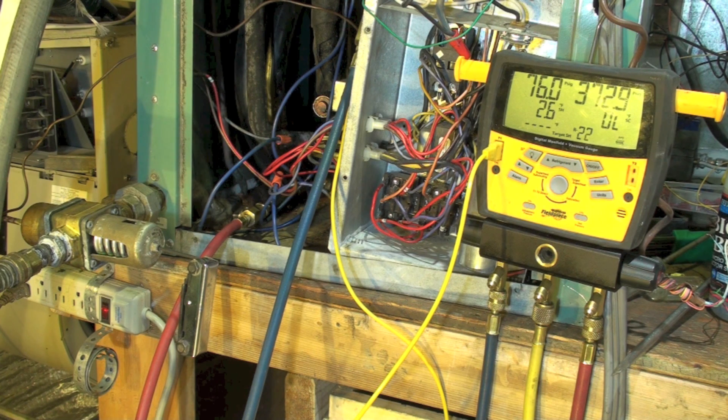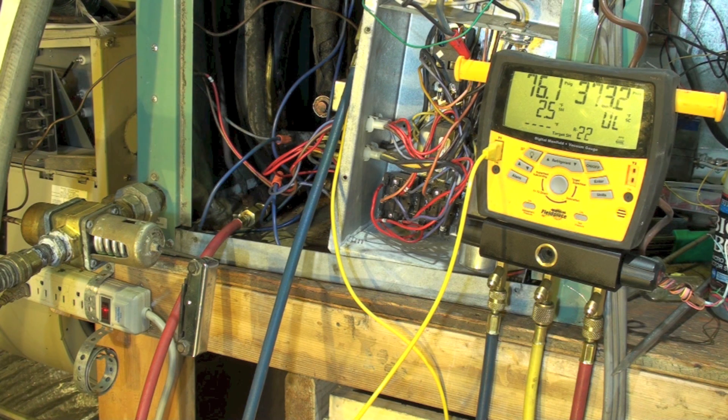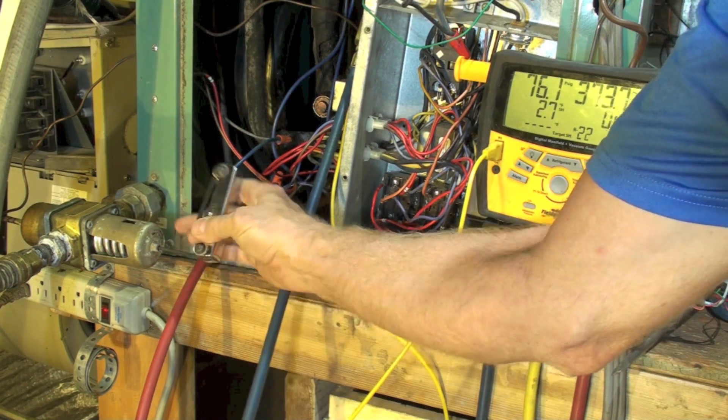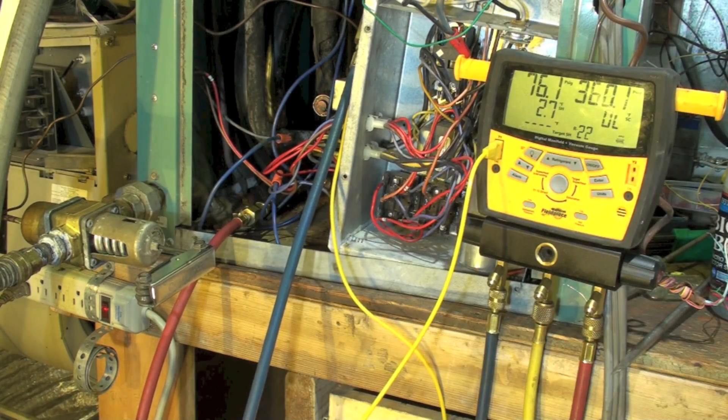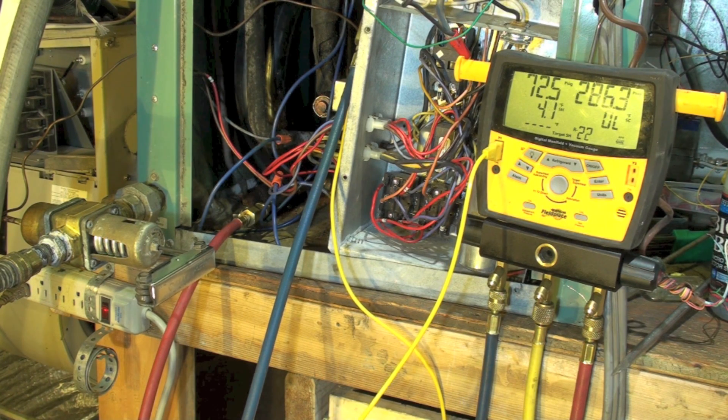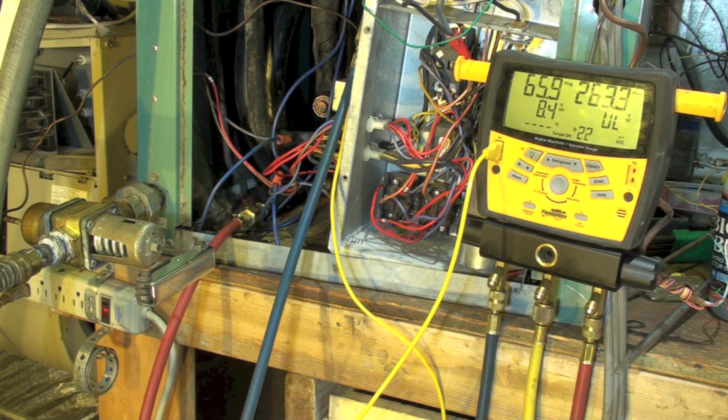So you can see 370 some pounds of head, 76 suction, superheat very low. Now I'm going to start adjusting this down to allow more water to come through.